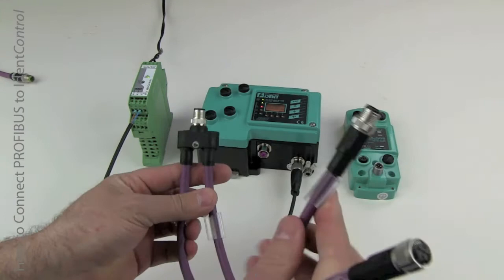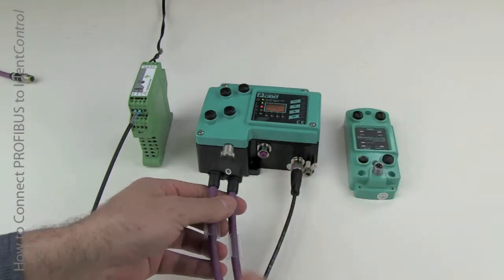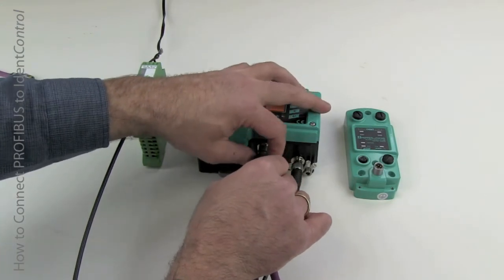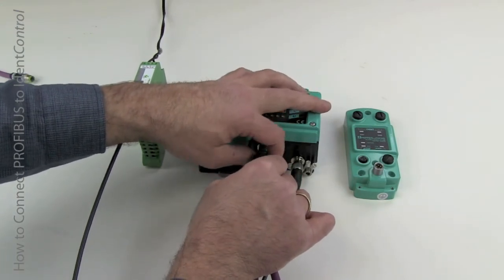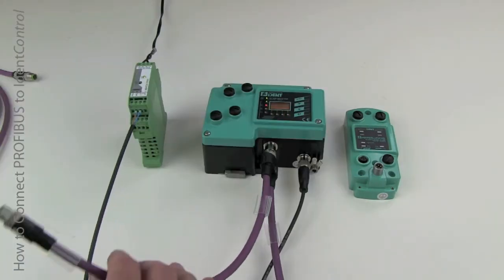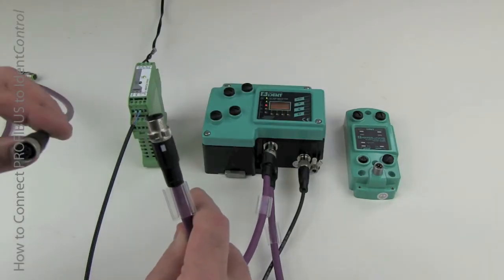Now, a little better alternative, just because it puts less stress on the trunk line, you can use a Profibus Y cable. So you, again, attach the Y directly to the controller, and then attach your trunk in and trunk out lines to the pigtails.